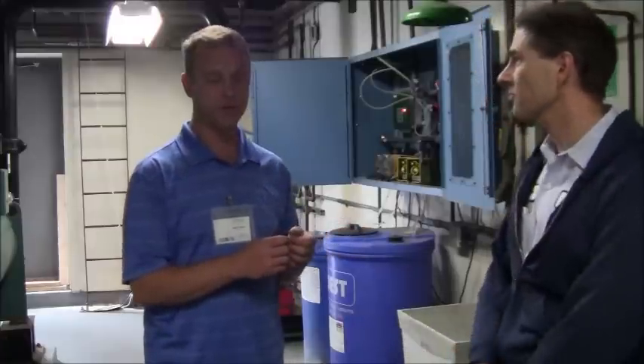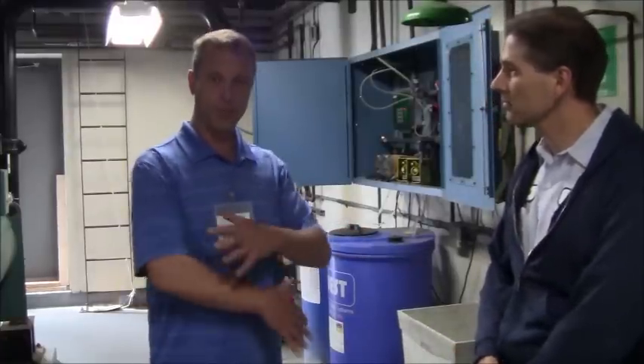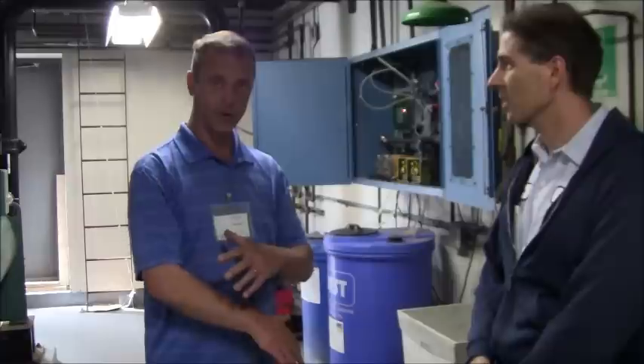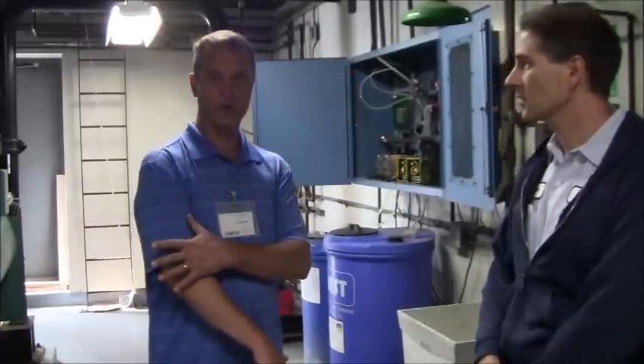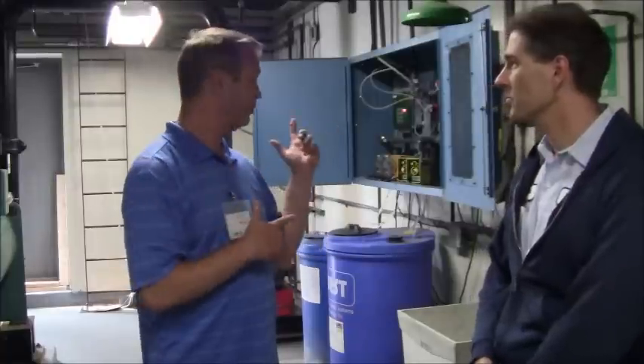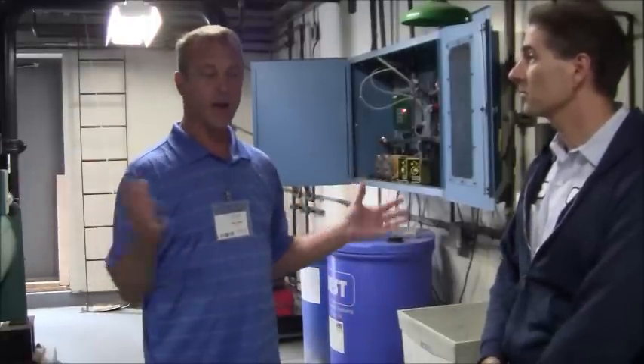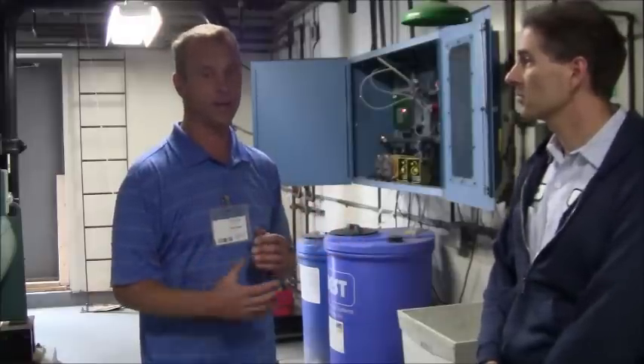Good point. And just to touch on what Ken just mentioned too, it's similar to when your body sweats and the wind blows over you. That cools your body, right? That's exactly what's happening in an open loop, like we were just talking about, where it's raining down through the fill and the fan is sucking the air in. It's also sucking in dirt and construction dust from the area, and all these particles are getting sucked into the cooling tower, which requires cleaning the cooling tower more frequently on an annual basis.